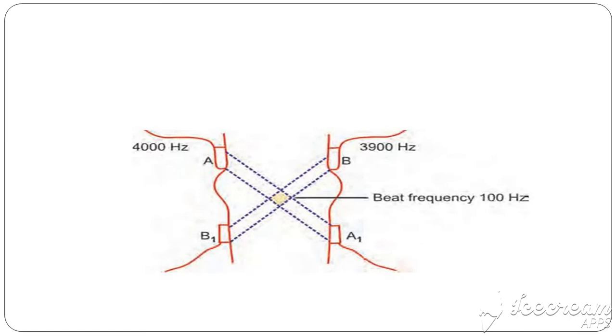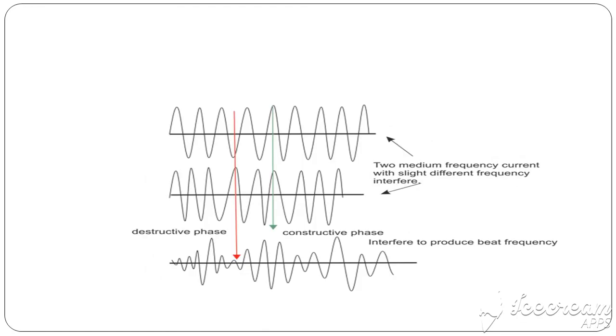And the beat frequency - we have to place the IFT electrodes in such a way so that the treatment area will come under the beat frequency. That's why the electrodes are placed diagonally in IFT. So these are the waveforms. Two medium frequency currents with slight different frequency interfere.